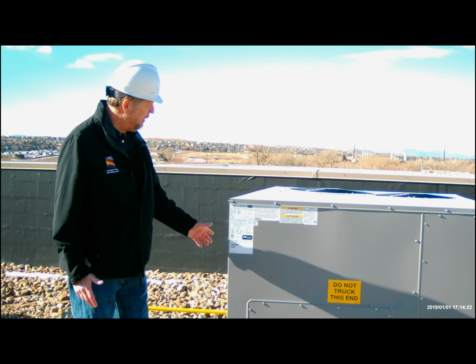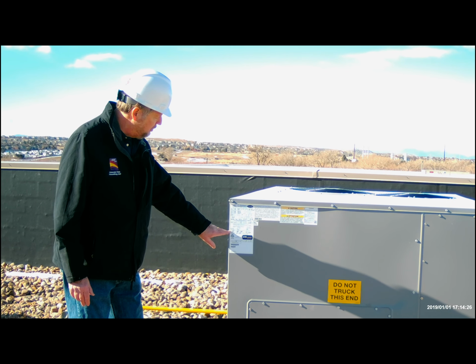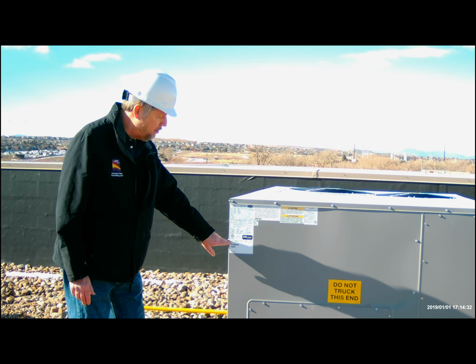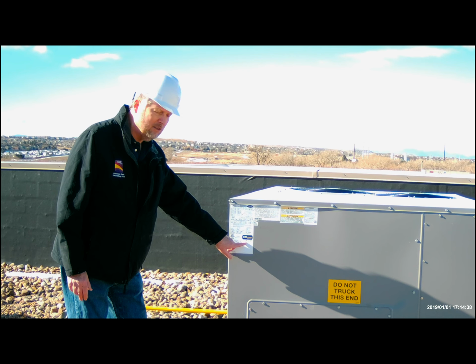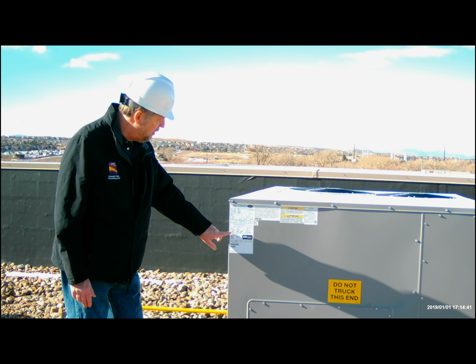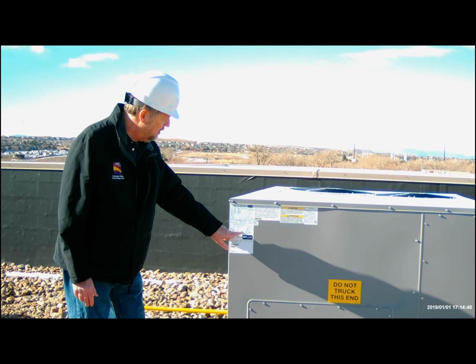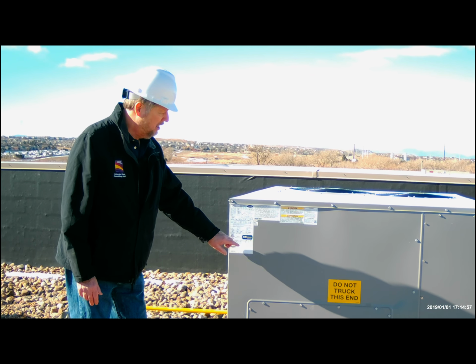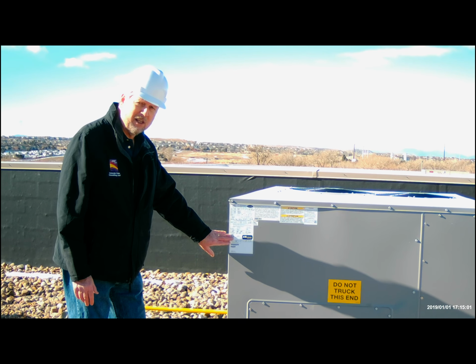So what I am looking at mostly is what will it actually do, what are my capacities. We look down here and start to look at our heating capacities, does that match what the plans say. We come down here to our cooling capacities and it tells us what those are, and what our efficiency is, and it does the same thing up here for heating capacity. In this particular case we've got 150,000 BTU input, 120,000 BTU output, at 81% efficiency. As long as those match our plans as far as efficiencies and capacities, I don't get too bent out of shape about the model number.